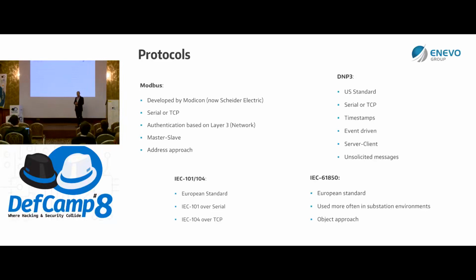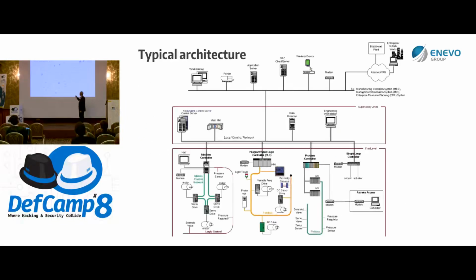It's a message that you need to send from one substation to another in under 40 milliseconds for them to trip the circuit breakers, to decouple the substation in case of a fault on the connecting line. Usually you have a fiber optic implementation to transfer that, otherwise it's going to take a while.